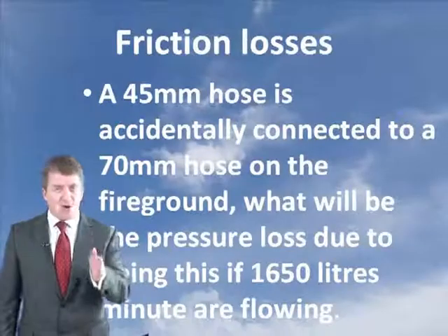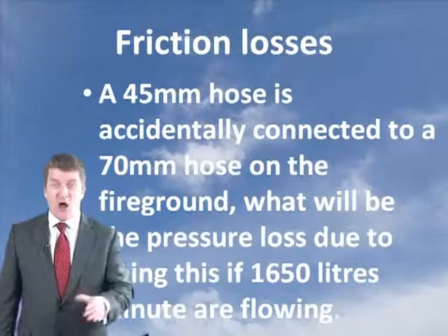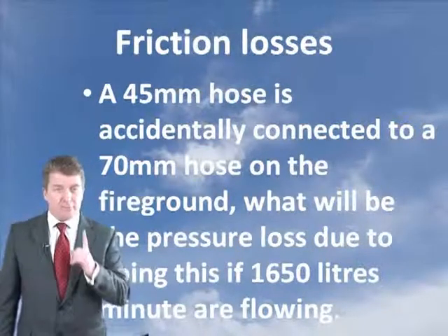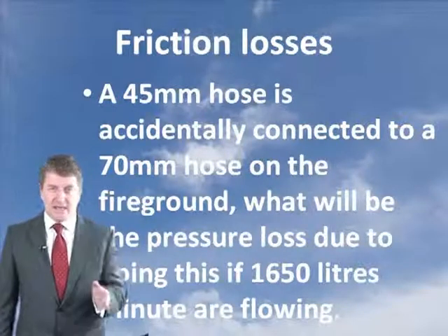Let's do one more example using these principles. A 45mm hose is accidentally connected to a 70mm hose on the fireground. What will be the pressure loss due to doing this if 1,650 litres a minute are flowing?